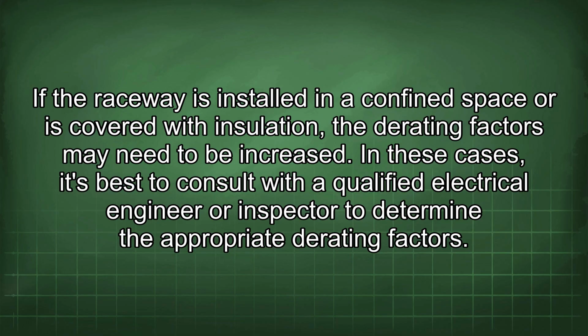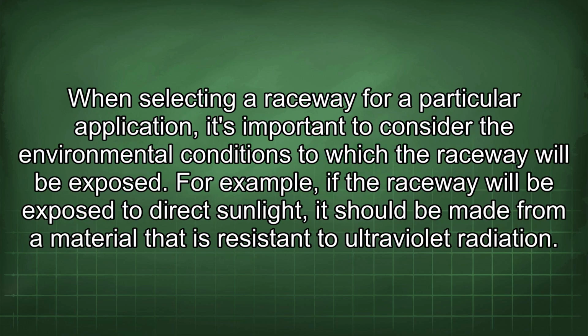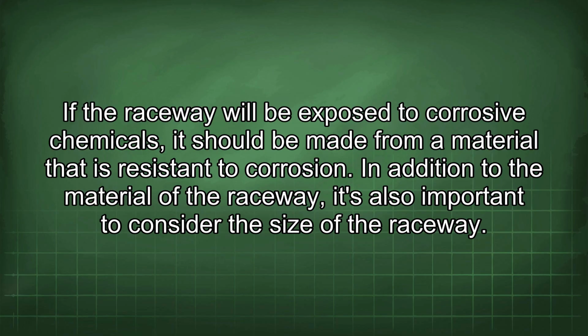If the raceway is installed in a confined space or is covered with insulation, the derating factors may need to be increased. In these cases, it's best to consult with a qualified electrical engineer or inspector to determine the appropriate derating factors. When selecting a raceway for a particular application, it's important to consider the environmental conditions to which the raceway will be exposed. For example, if the raceway will be exposed to direct sunlight, it should be made from a material that is resistant to ultraviolet radiation. If the raceway will be exposed to corrosive chemicals, it should be made from a material that is resistant to corrosion.